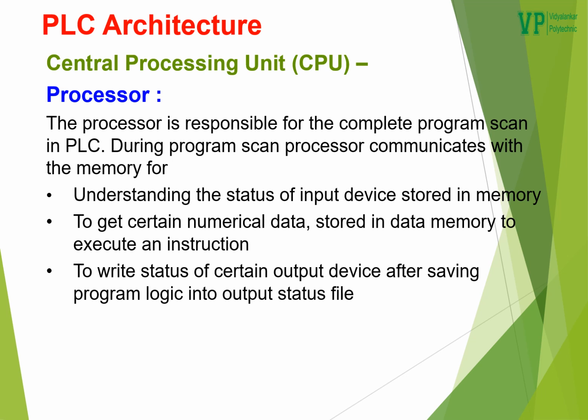Well, it means if you have inputs and outputs connected to the PLC, the moment you operate any one of the inputs, this is scanned by the processor, and the information about the input device is updated in the input status file. On execution of the program, this information of the input status file, and depending upon the ladder logic written, the processor sends a signal to the output status file, and from the output status file this signal is sent to the output device, which is connected to the output module.